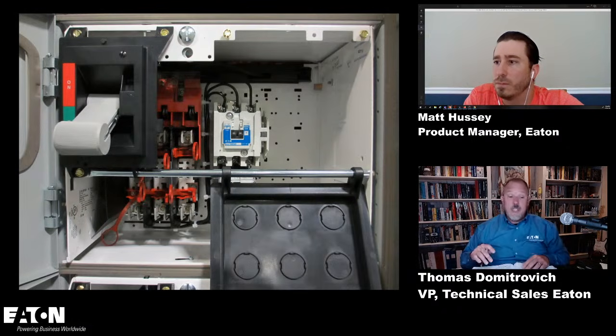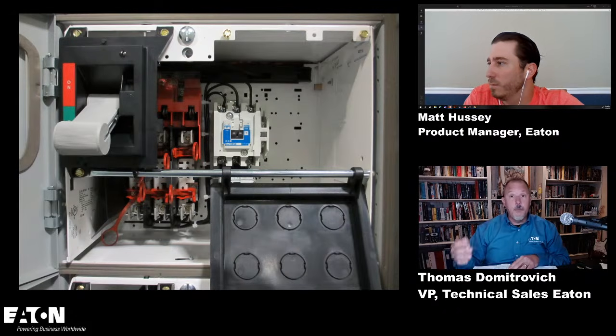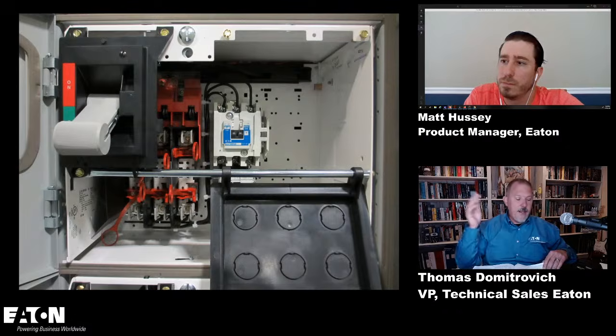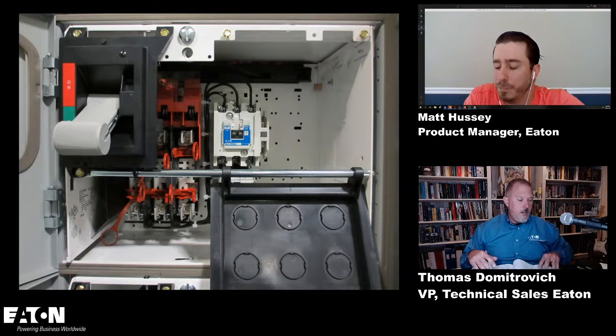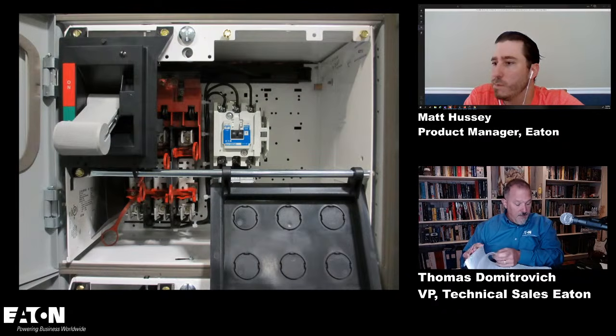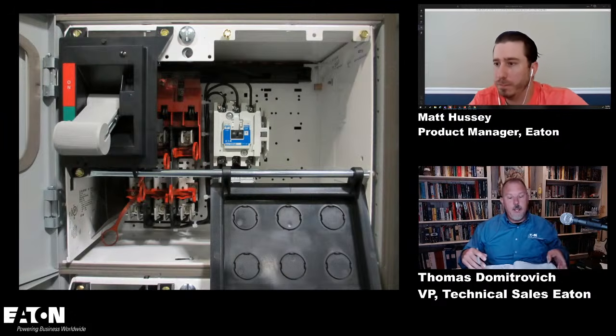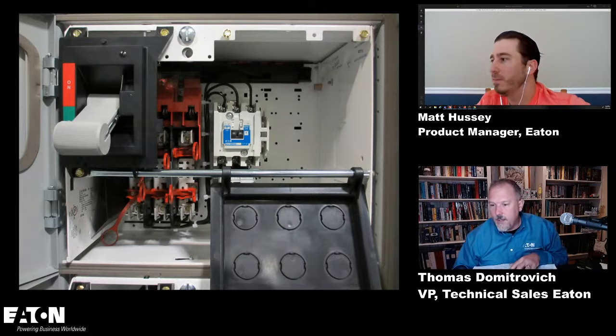I know some jurisdictions will, like Donnie Cook in Shelby County, Alabama. They have a rule that says all products are going to be listed when they're installed, and he has the ability to say you're not using unlisted product. But if you go back, I can't remember the section. It's back in 110. I know 110.3(B) is what they use for looking at manufacturer's instructions, but I think it's in 110.3 that talks about examination. Anyway, Brian or one of these guys will probably know.